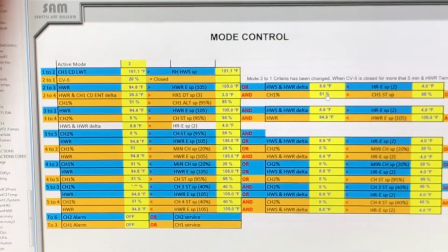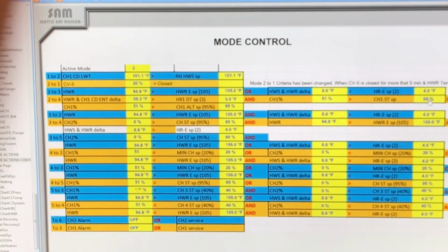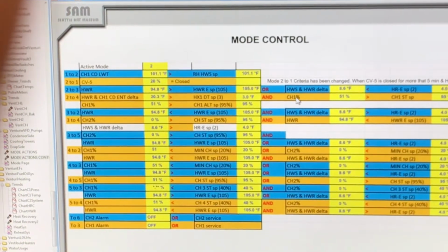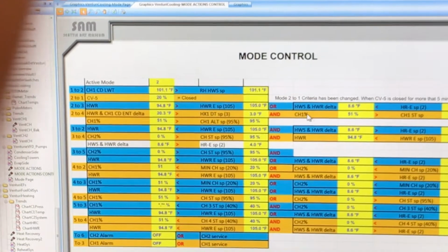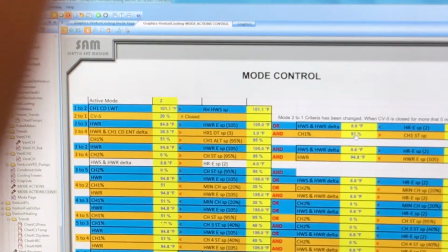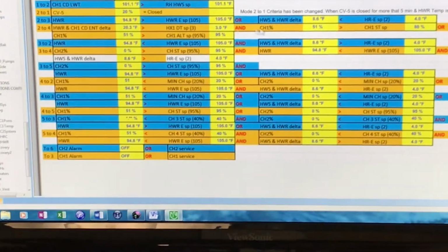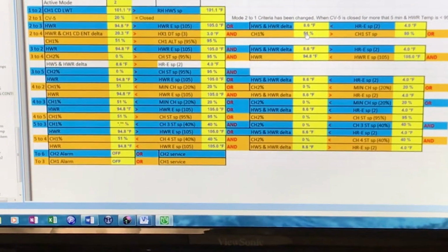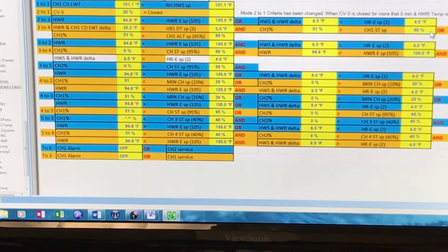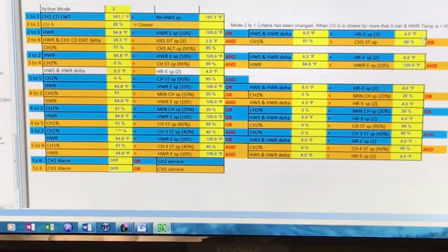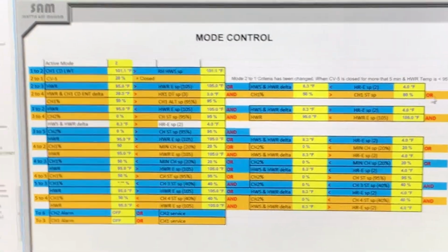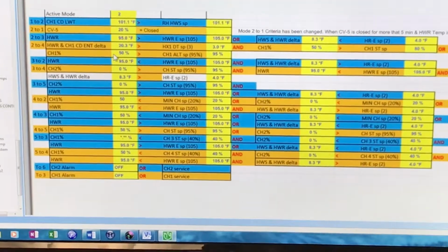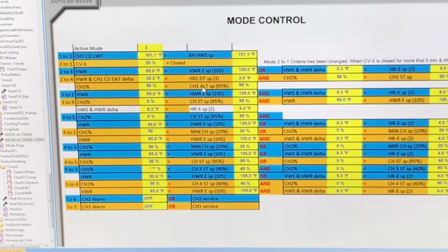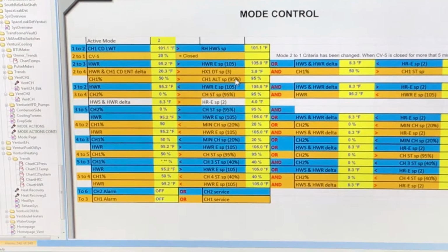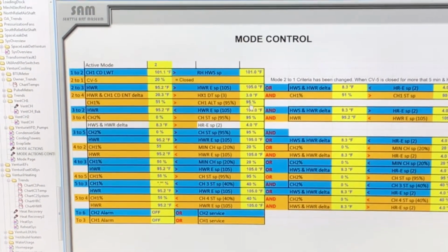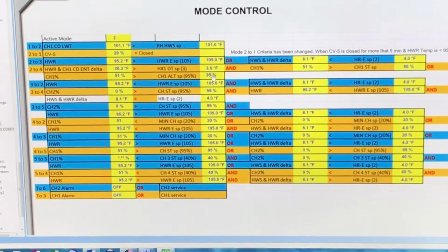Chiller 1 load percent, which is 51, has to be greater than 80. So it has to be above 80% on chiller 1, with the delta being higher, and greater, which it is. So if chiller 1 got up to 82.4%, it would go from 2 to 4. Or, we have another or statement here, and we go down to the next one. Chiller 1 load percent, 50%, is greater than the chiller 1 alternate load set point of 95, which it's not. It's only at 50. Okay, so explain to me, just to make sure you got it, how that works.